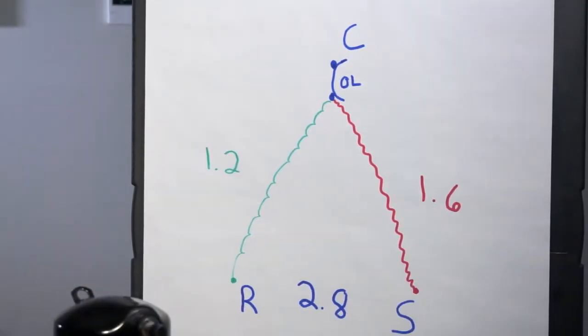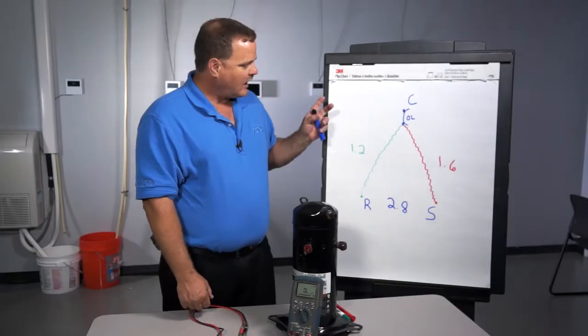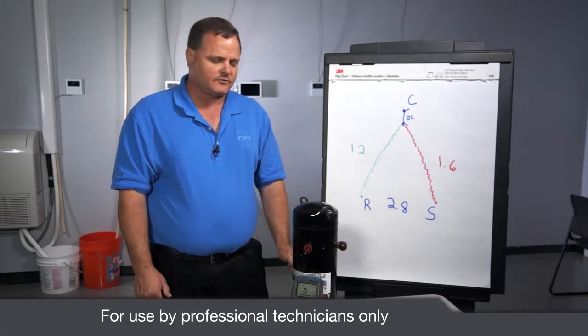what I've always done and makes it easy is draw the terminals out on a sheet of paper. And as you can see here, I've got a drawing of the windings of a compressor.